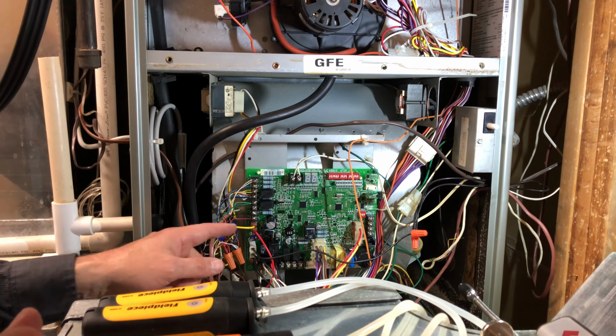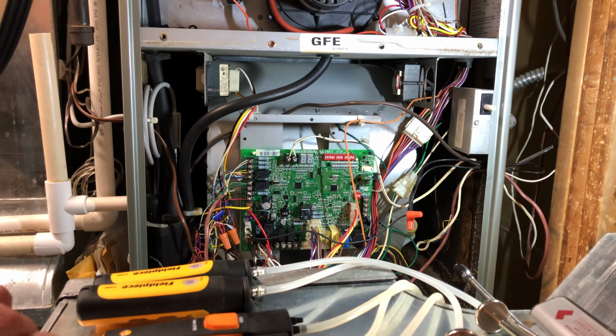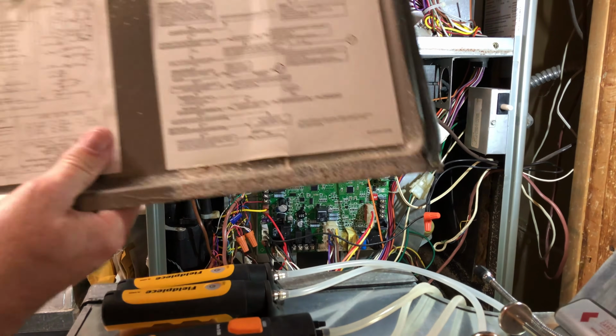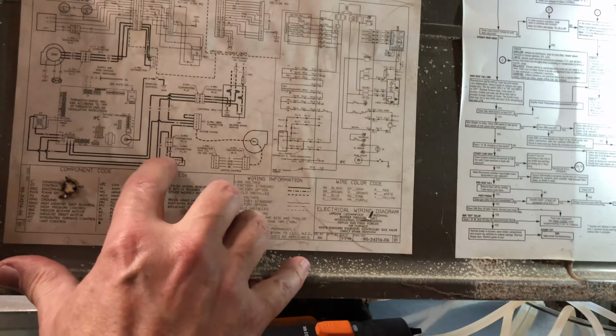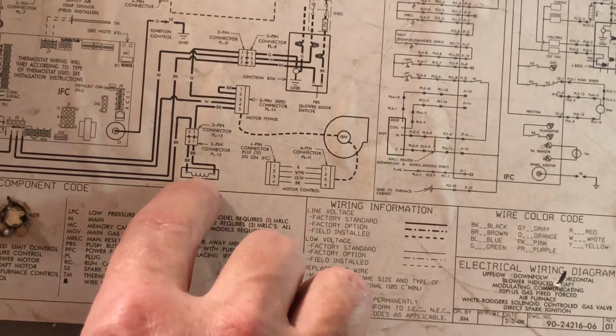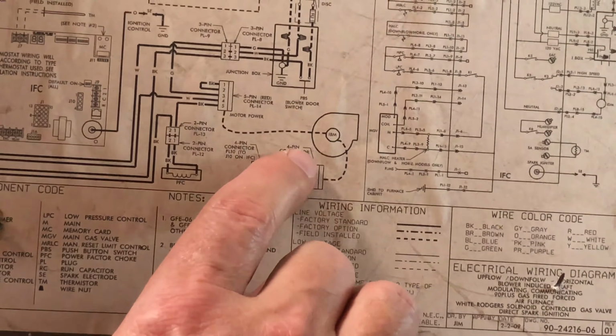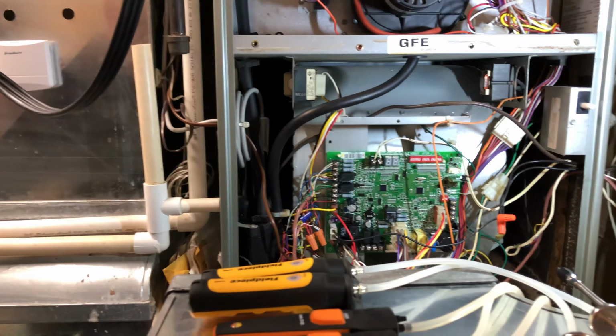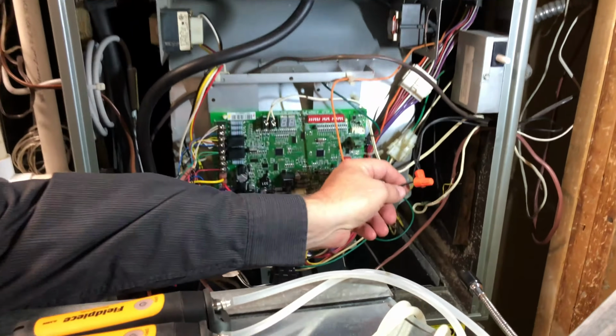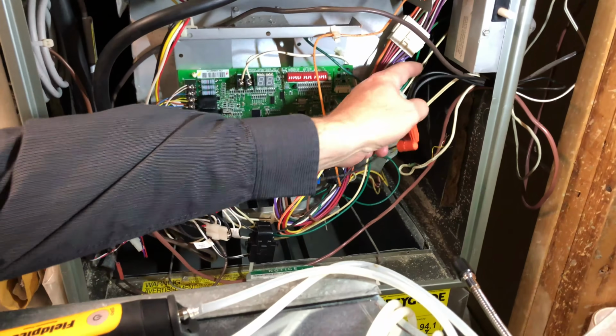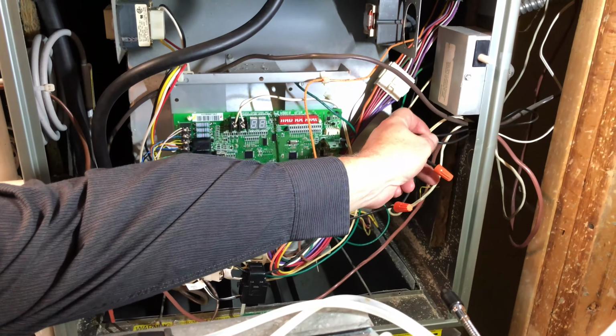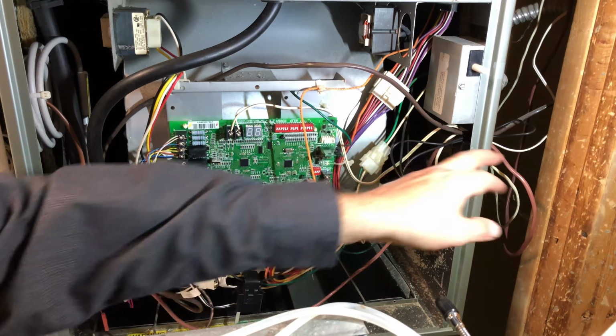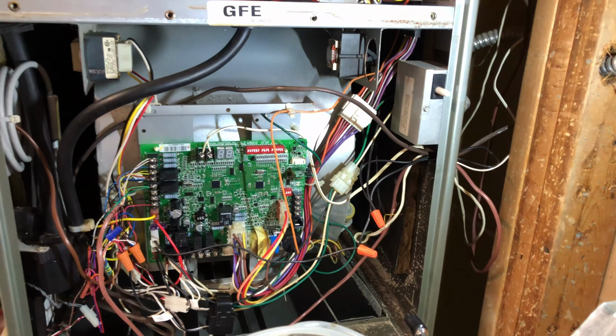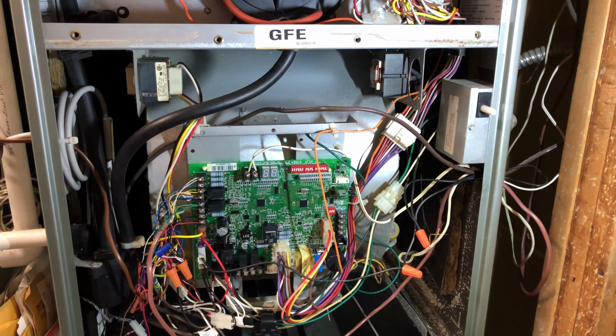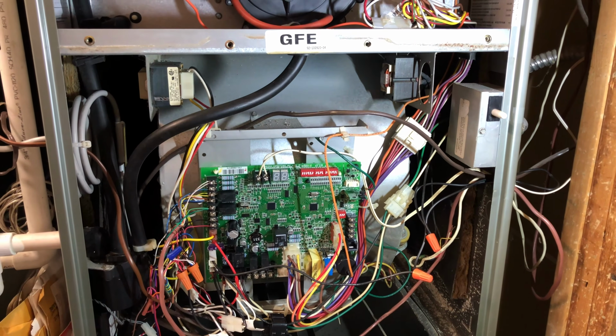Then another thing I do, this is an ECM motor, and if you look at the wiring diagram here, I don't know if you can get in close on that, but basically this is the hot wire coming in, and it goes through a choke, and then it feeds into the blower motor. So what I did here, in order to get blower watt draw, is I just cut the wire, add a little black wire, and I fed this through the plastic grommet on the side. So I can measure amps of my blower here with the door on, and then I'll just pull this back inside when I'm done with it and rewire nut the two wires together.